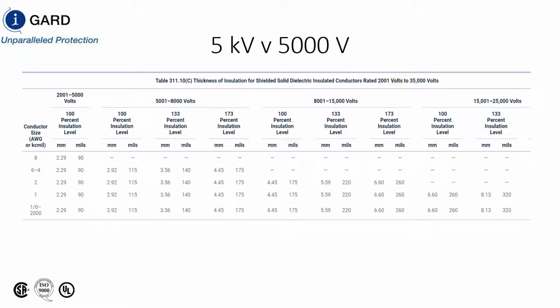I bring this up because we've had some customers who have come to us and they wanted to convert a 600 volt system from an ungrounded system to a high resistance grounded system. They went to a cable manufacturer, and the cable manufacturer says they need to recable everything at 2 kV to compensate for the 173% rated insulation. It's not necessary. At 600 volts or low voltage, there is more insulation in the cable to protect the cable against mechanical stresses that it far exceeds the electrical rating.